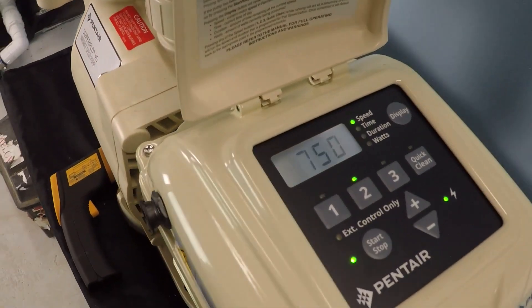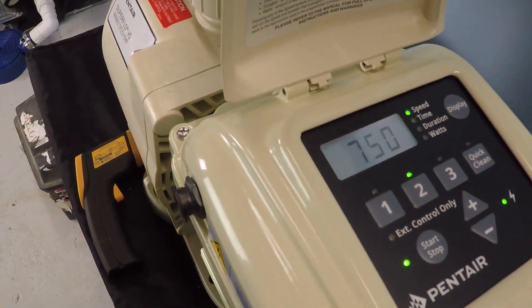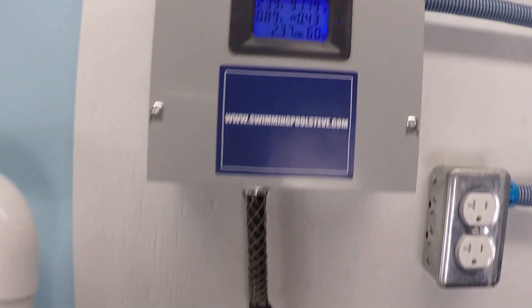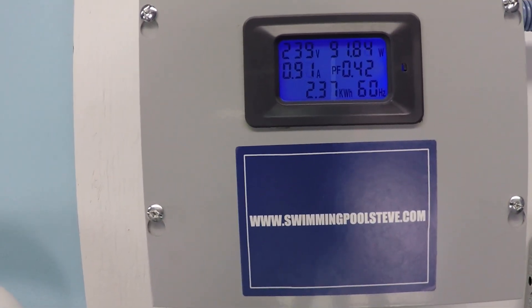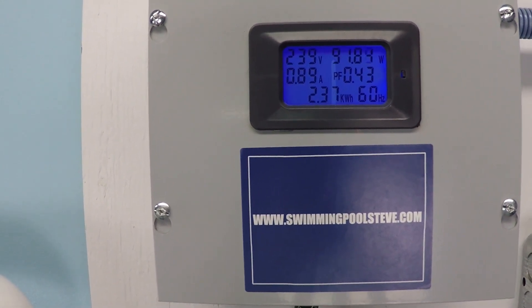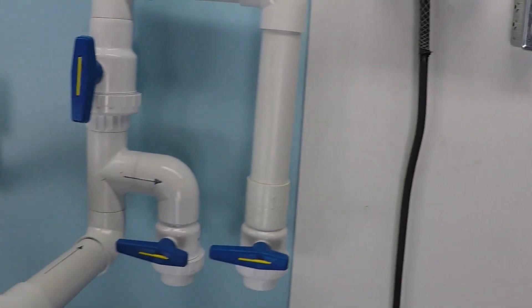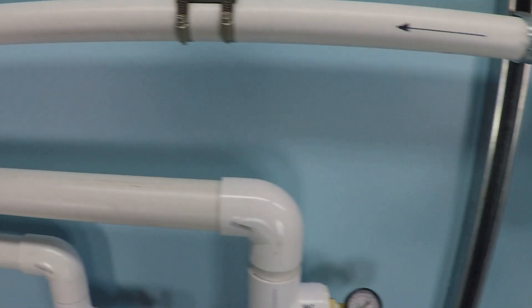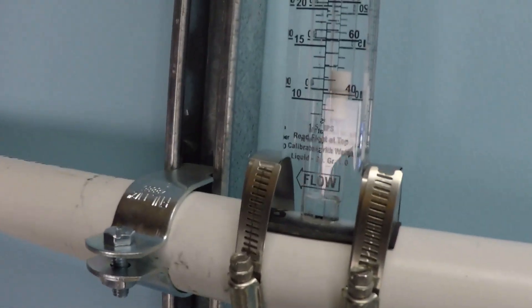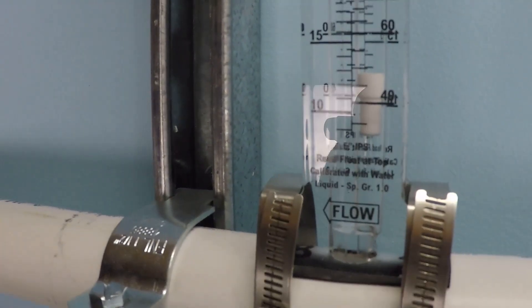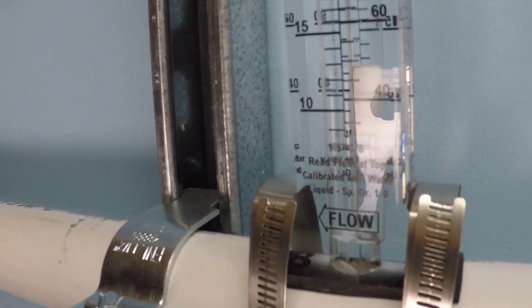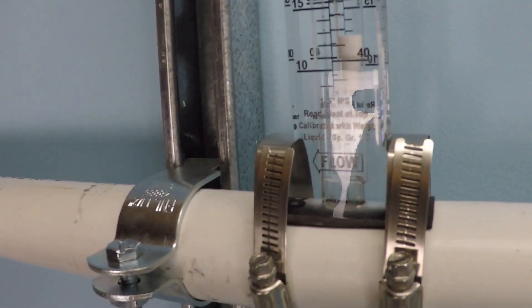Let's go, already running. 750 RPM, electrical consumption at that rate is 0.9 amps, 91 watts. Flow rate under this condition, just about 13 gallons per minute.